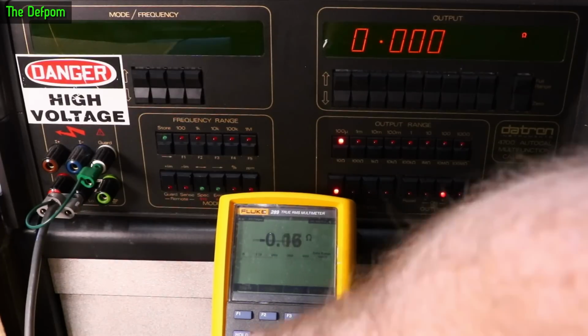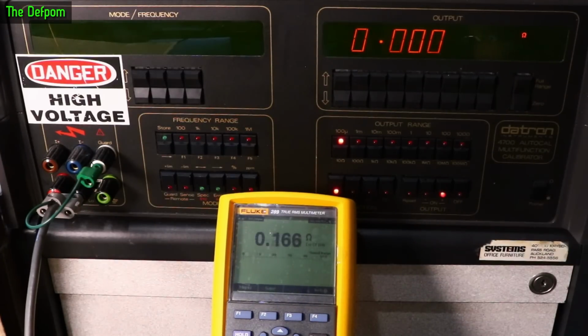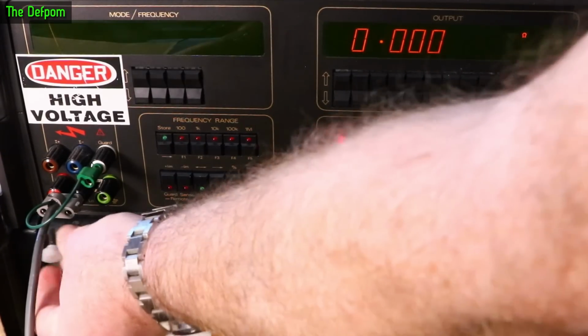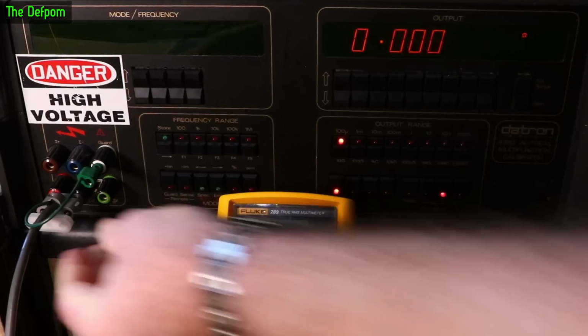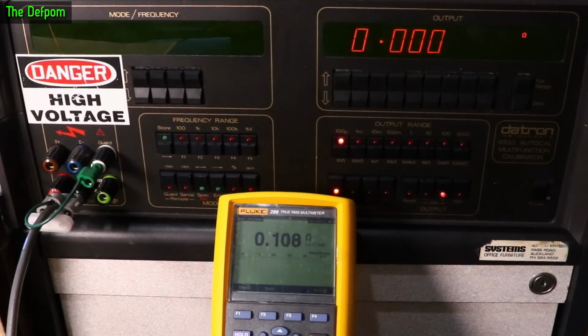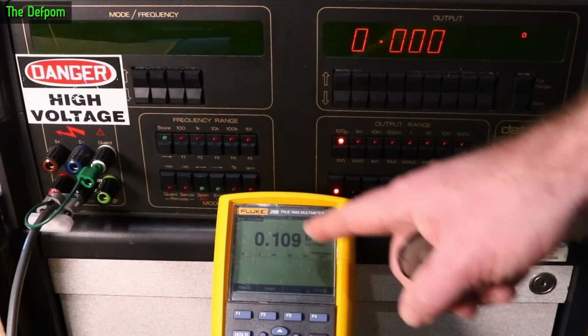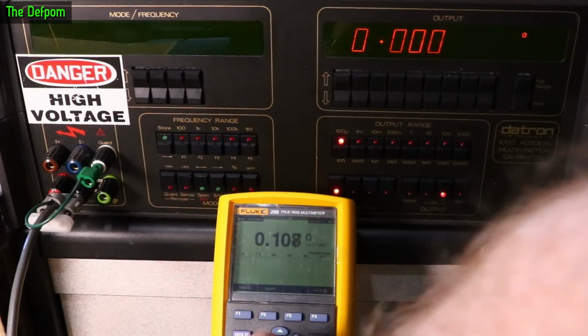And while I'm here, actually might go down to the 50 ohm range as well. There's a 50 ohm low ohm range, which is settling down. So there you go, the low ohm range actually settles down to a negative value. That's interesting. It's even better than what the factory had for a short then. We'll take that back out. We'll short it back across the input of the actual calibrator, which will change things a little bit, because that's then the lead resistance. We get about 0.1 ohms there on that range.